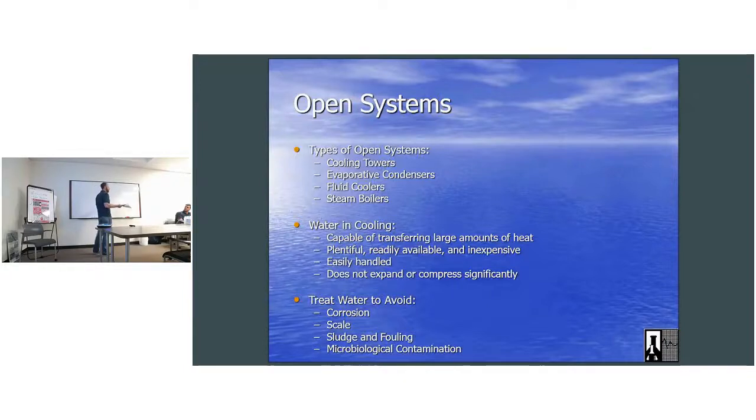Do you guys know, raw water would just essentially chew through any cooling tower you had, coated or not? A lot of people think, oh, well, it's coated, it'll be fine. But it's not just a cooling tower, it's where it's going. You've got water source heat pumps down the line. If it's just in a cooling tower, it's cycling up over the coil. With an evaporative condenser, it's just coated, but it'll chew through that coating, and then you'll start eating up everything, and you'll be covering it all in scale. So that's why we build the cycles of concentration, and we treat that with the chemical. We'll talk about the chemicals here in a minute. So, any questions so far? That's why we do it.